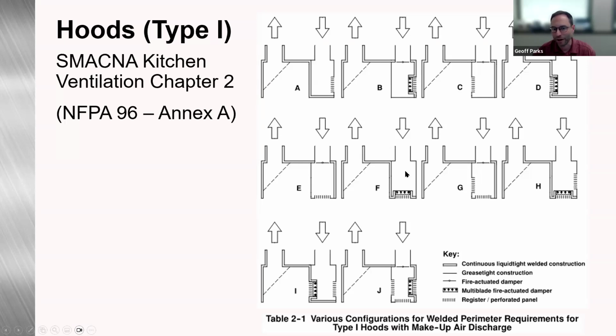As you can see, detail F, this makeup air is not penetrating the continuously welded construction, so no fire dampers required, but the actual grill is penetrating that, so a multi-blade fire actuated damper is required. And this is also found in NFPA 96 Annex A. Same details are in there as well.